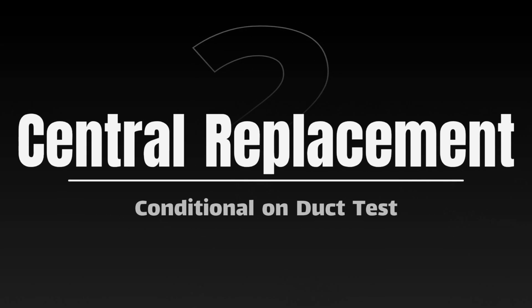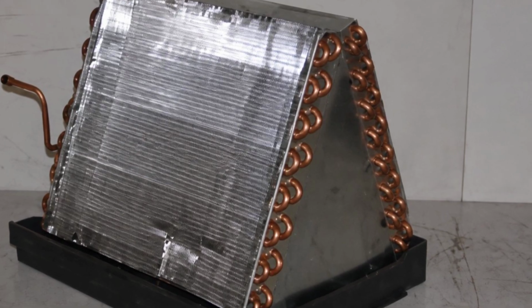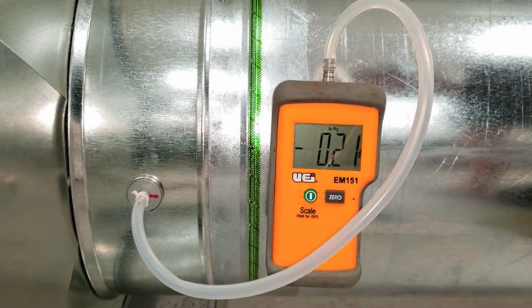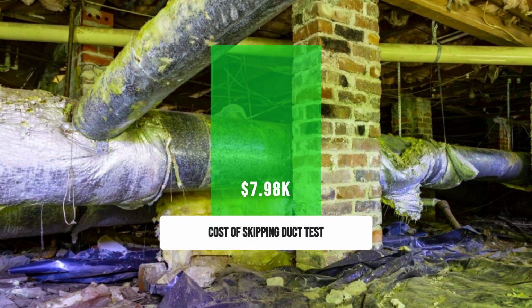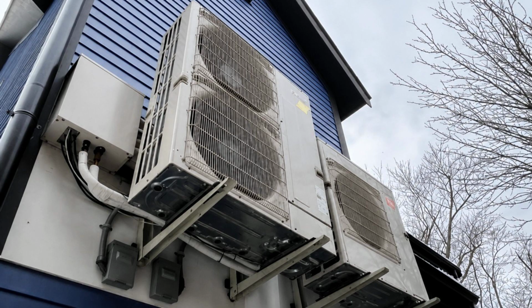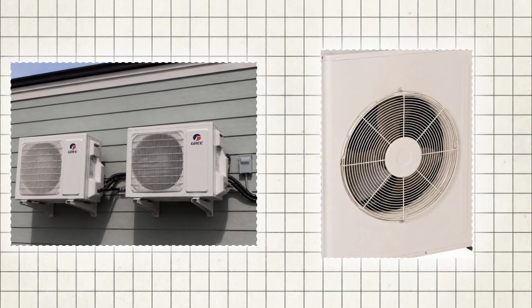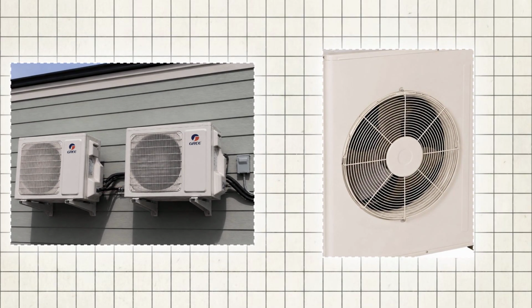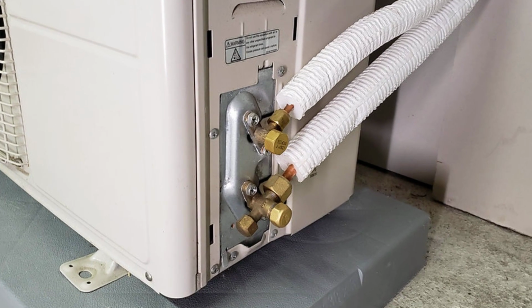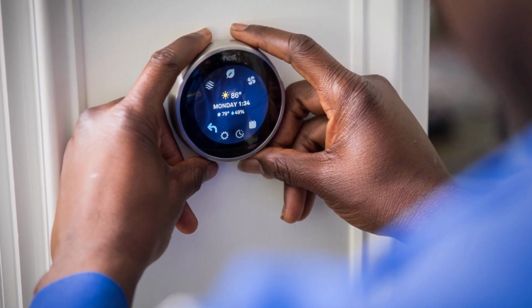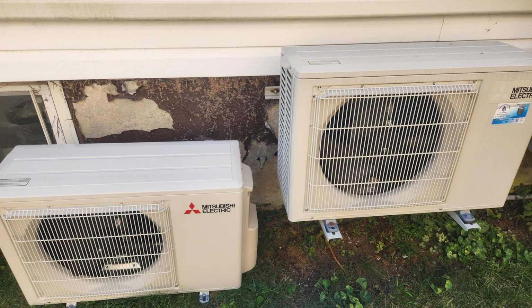Second pick. A straight central replacement into ducts you've actually tested. Boring and correct. 1 coil, 1 drain, 1 thing to maintain. But it's entirely conditional on that test. Skip it, and you recreate the $8,000 spread. Third pick, and the one I'd spend my own money on with no ducts. 2 separate single-zone systems instead of 1 2-zone system. Similar price, no branch box, no shared minimum capacity, and 1 failure takes out 1 room. The limitation, you need 2 spots on your exterior wall.